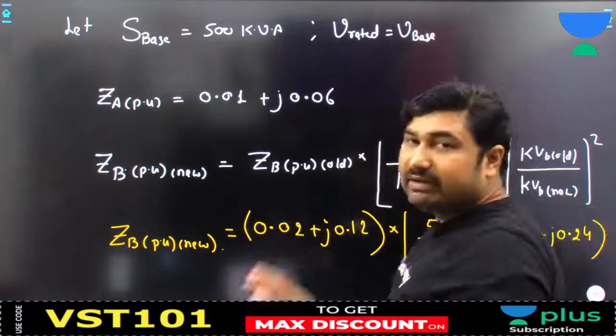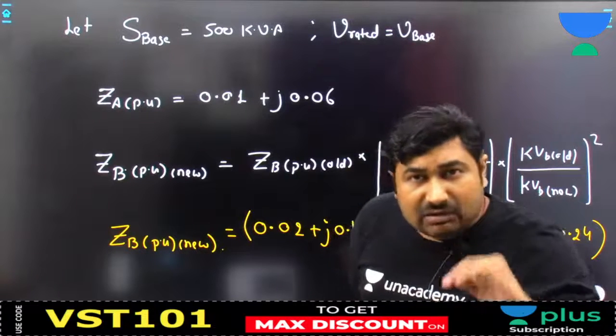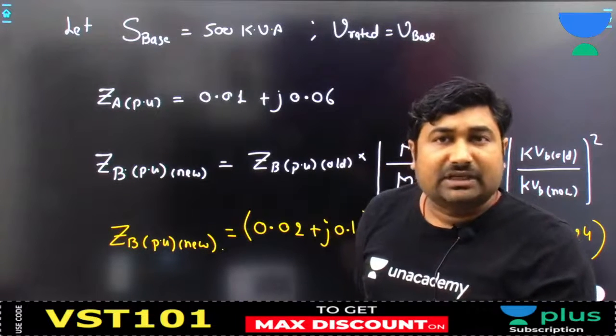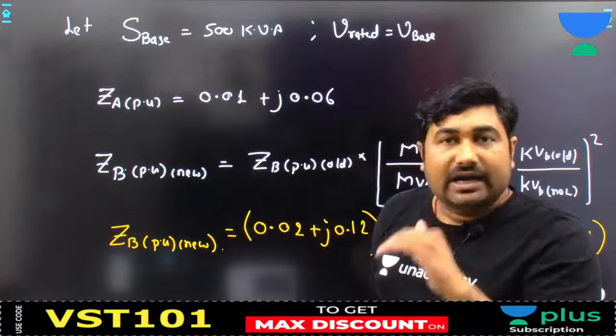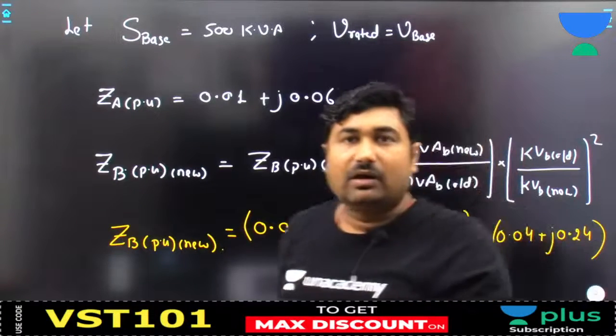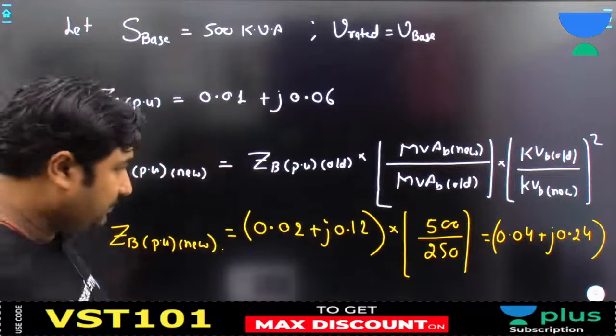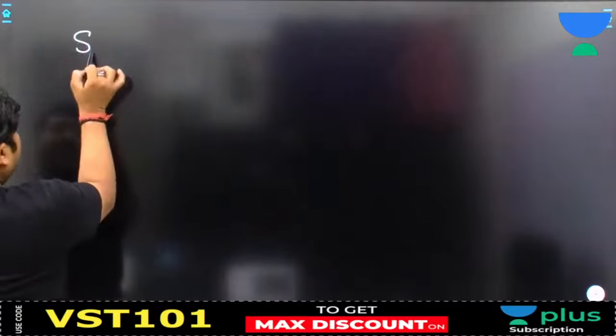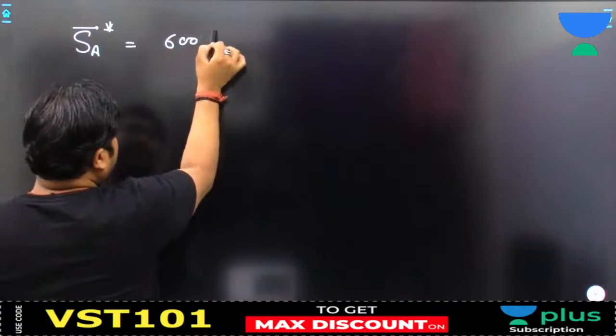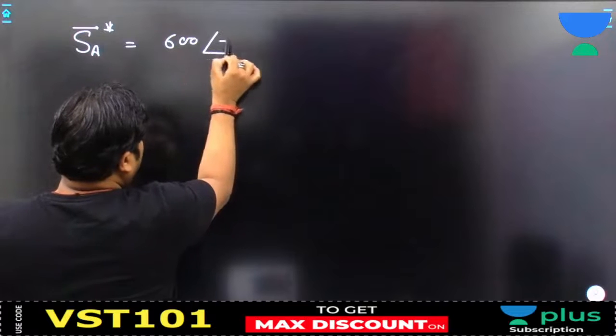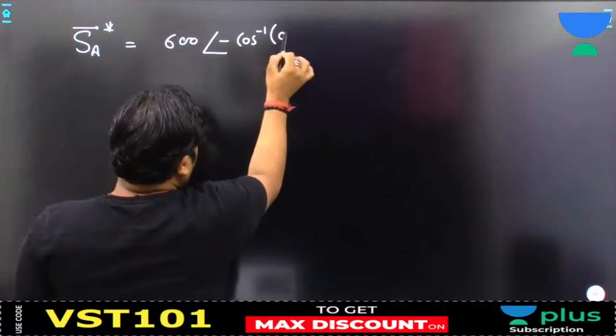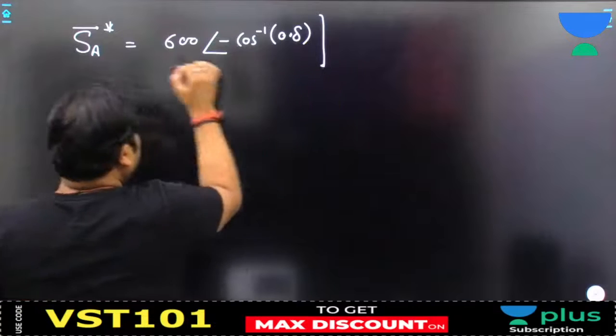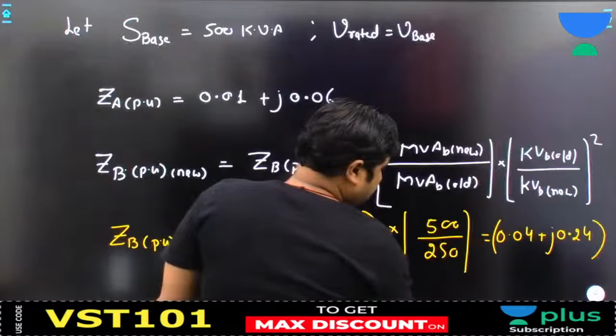Yes sir. Current divider rule. We have calculated the KVA delivered by each of the transformers from the current divider rule only. Already I have derived that in the last lecture. Now please see. So sir, KVA delivered by transformer A conjugate will become 600 KVA, that is load KVA, at an angle of minus cos inverse 0.8. Why am I taking minus? Because SL conjugate, we have to take SL conjugate.